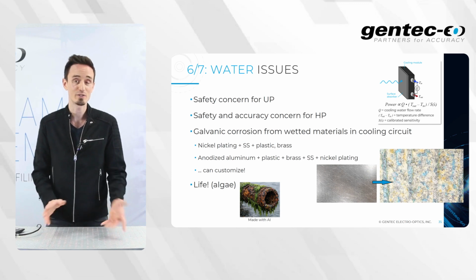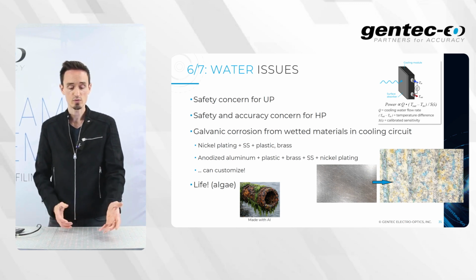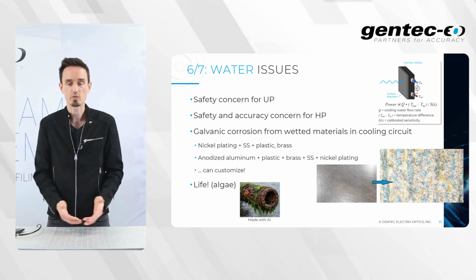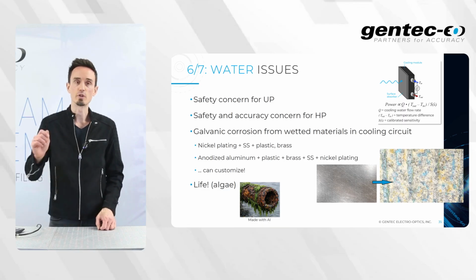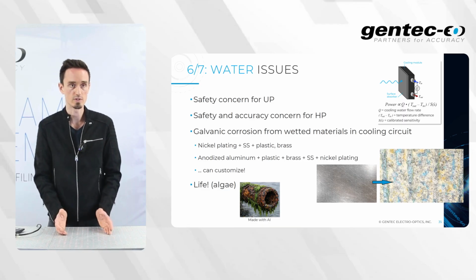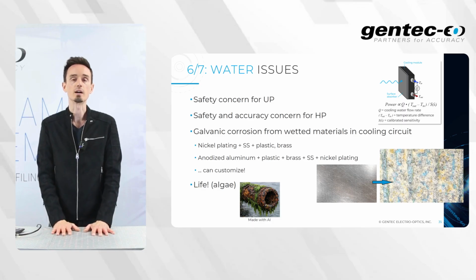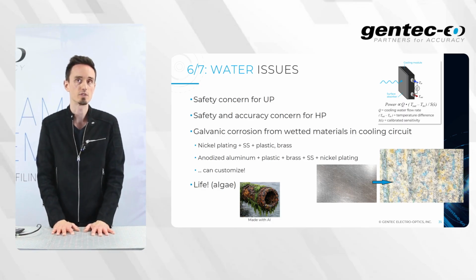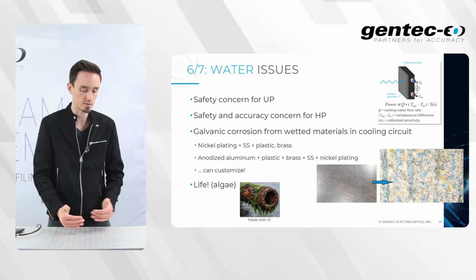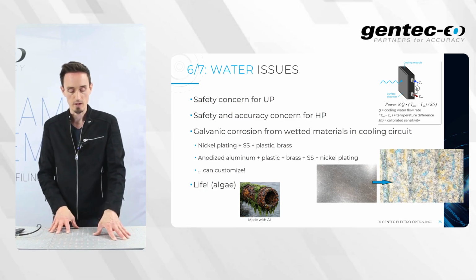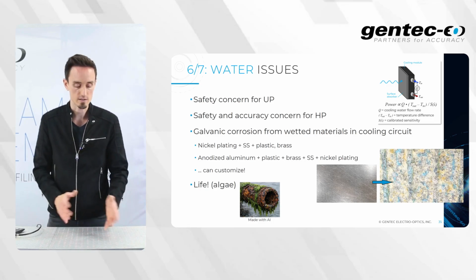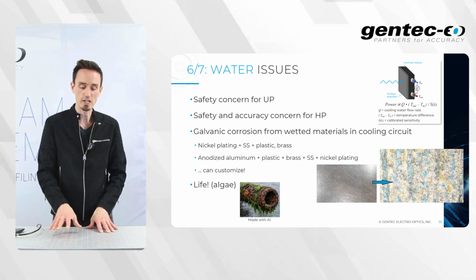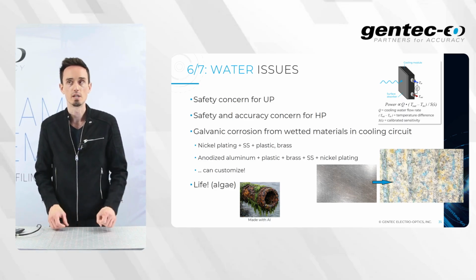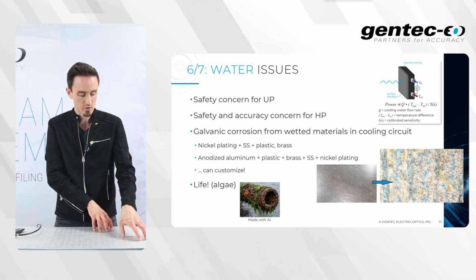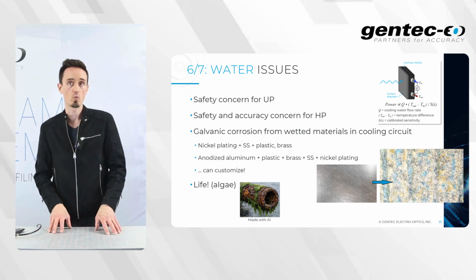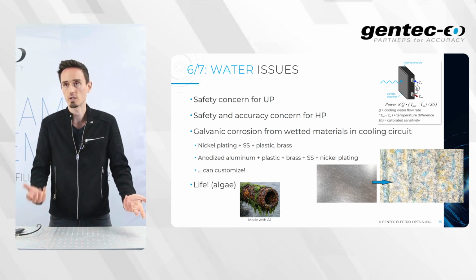Okay, next, water issues. Yeah, water is used for cooling down detectors, making them safer for use and for your system. For those thermopile detectors, using an array of thermocouples and disks, water represents a potential safety concern. If you do not use enough flow rate or the right temperature range, you could get some overheating and some damage to the detectors. That's one thing. For those HP detectors, the water-based calorimeters, again, we're relying on water temperature measurement and water flow rate measurement, so water is used for both safety and accuracy concerns.